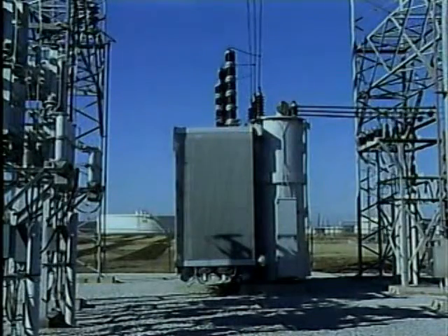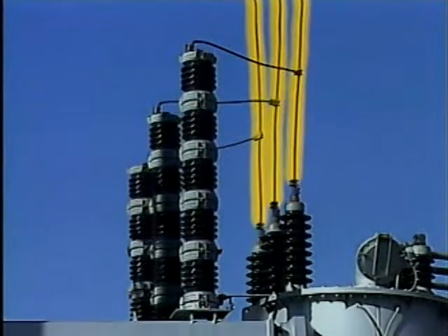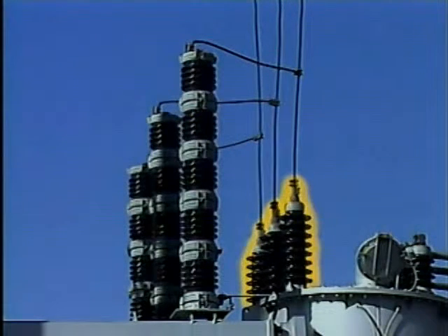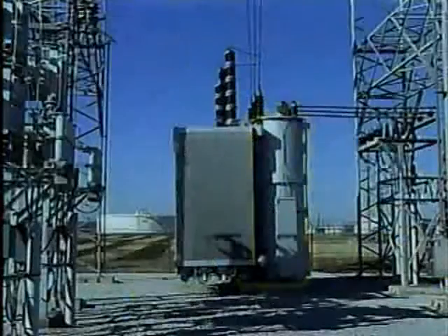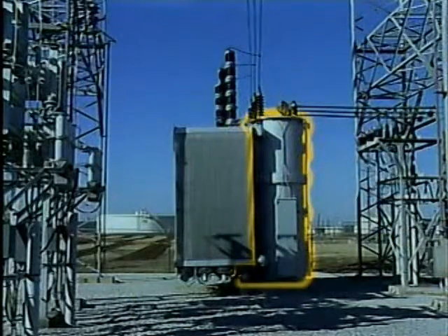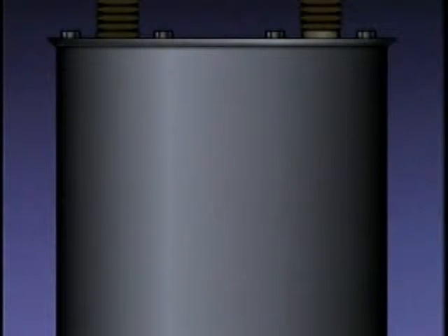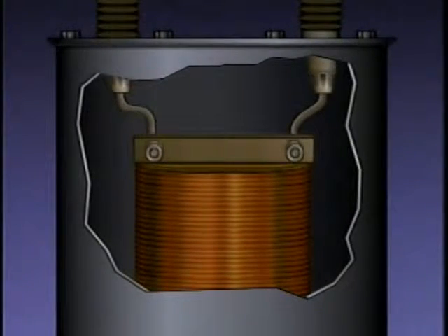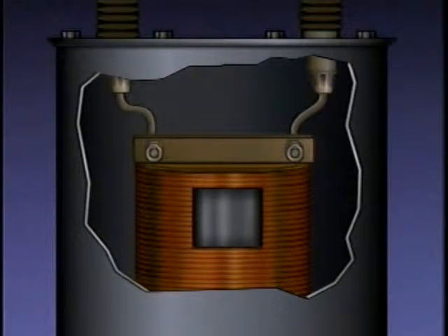Different kinds of transformers can be used to increase or decrease voltage from one electrical circuit to another, and the components that make up these transformers can vary as well. Let's take a look at some basic transformer components. Starting with this typical substation transformer: electricity enters the top of the transformer through power cables. Bushings are used to insulate the cables from the transformer casing. The casing provides a housing for the internal parts, and inside are the windings, usually mounted on an iron core which concentrates the magnetic field produced in the windings.